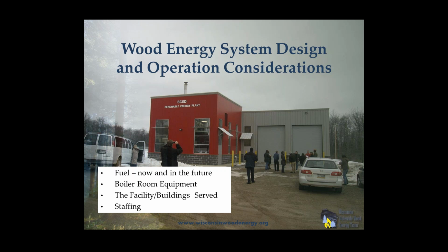And then boiler room equipment is another consideration, exactly what types of systems you want or what kind of pieces you need in the system. You need to look at the facility and building served, and you need to talk to the owner about staffing. Some of these institutional places now, they've got a heating system where it's just there and you ignore it. We have other places who have full maintenance staffs, and they're very comfortable providing additional services like raking ash or handling more oversized pieces, or just being more hands-on. So a real consideration of the design of the system is what exactly does the owner expect, what's acceptable to the owner.